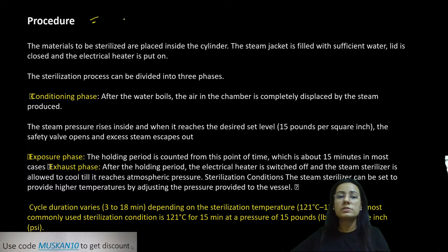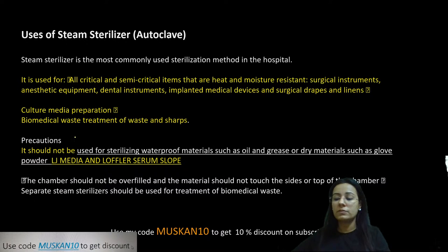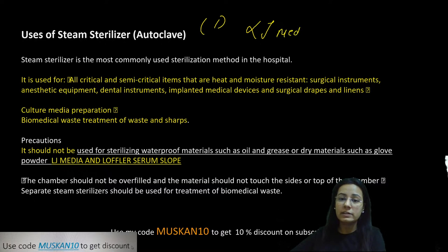Now coming to the procedure, there are three phases we have seen: conditioning, exposure and the exhaust phase. No need to go into the detail right now. One more thing is that it is used for the sterilization of the culture media, for biomedical waste management, and for critical and semi-critical instruments, the Spalding classification that we read about, but it is not used for the LJ media.